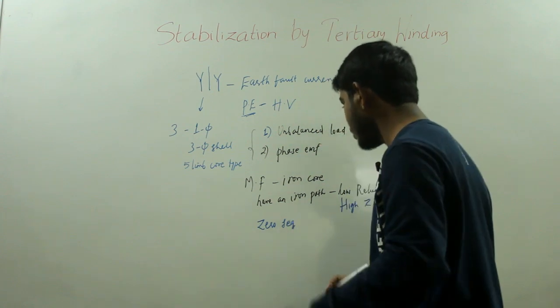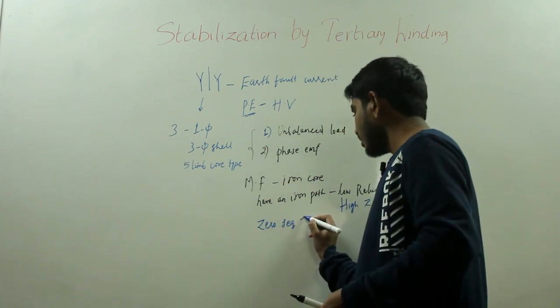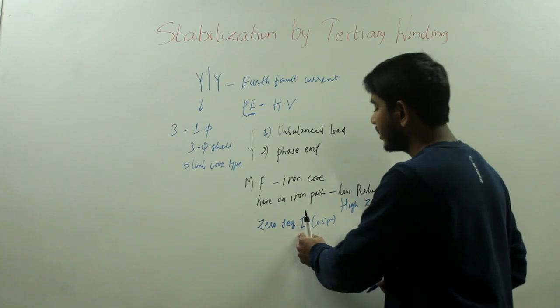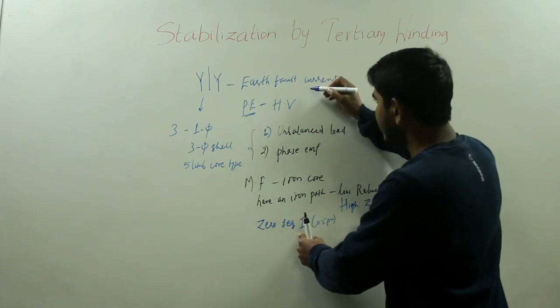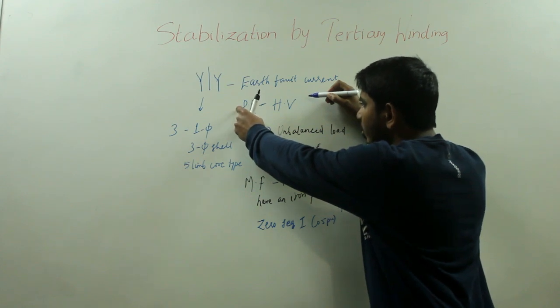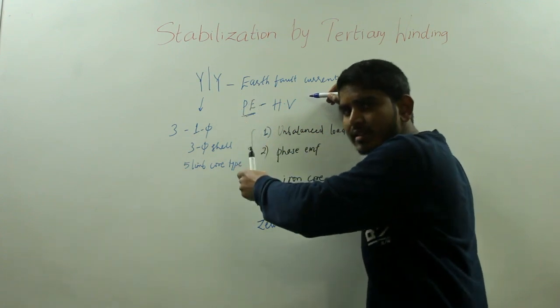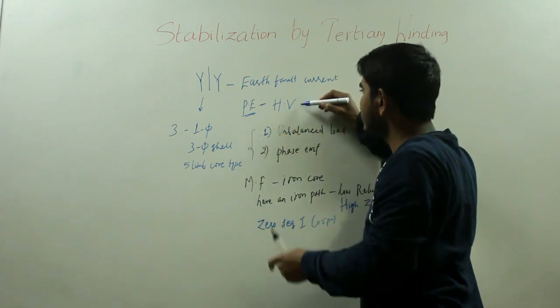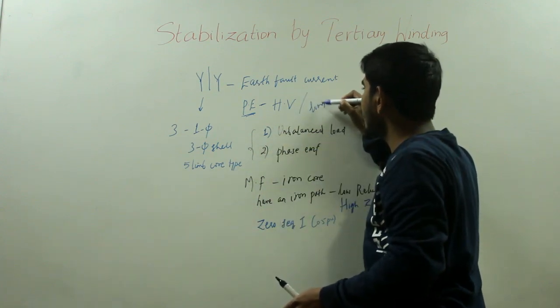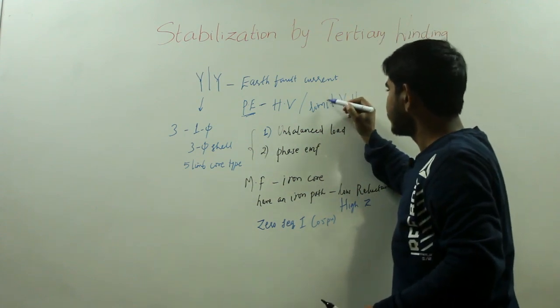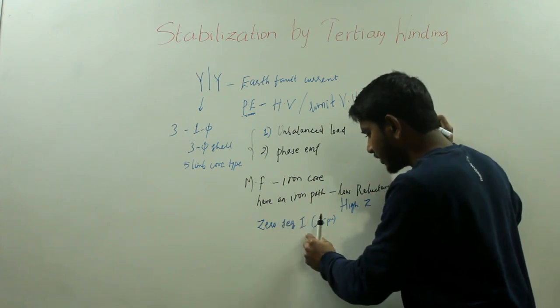The zero sequence impedance is very high — around 0.5 per unit. When this zero sequence impedance is very high, your earth fault current may be insufficient to operate your protective equipment. When you cannot operate your protective equipment in the case of an unsymmetrical load, you may not be able to suppress harmonic voltages or limit the voltage unbalancing. So you have to overcome this zero sequence impedance.